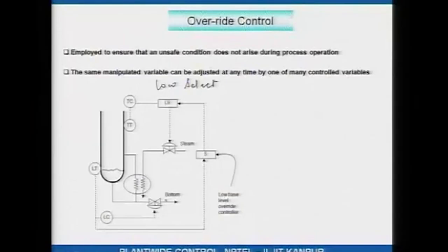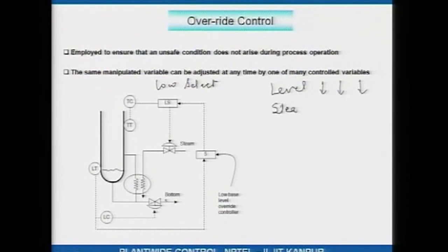The tubes in the reboiler must always be dipped in liquid; no liquid inside the reboiler is an unacceptable condition because then the tubes may get burnt. To prevent that, if the level is going down and continually decreasing even as the bottom valve is fully closed, you would like the steam to be reduced — you would like to pinch the steam valve.